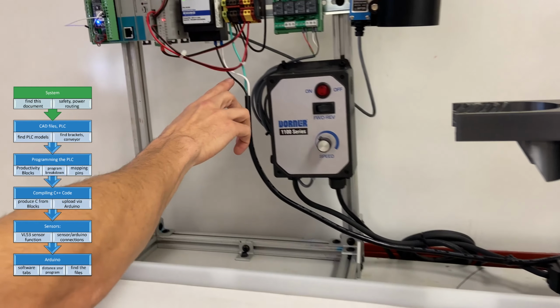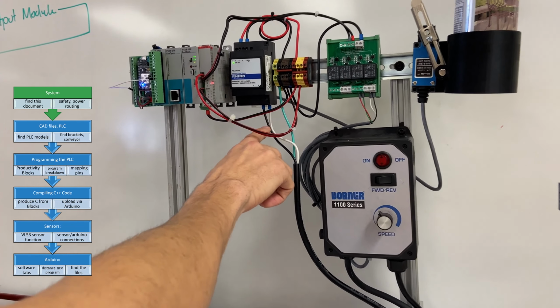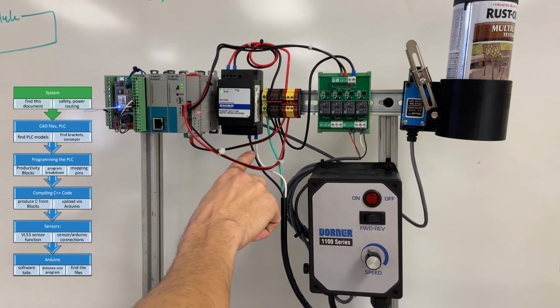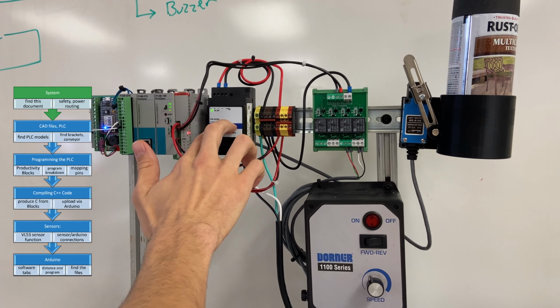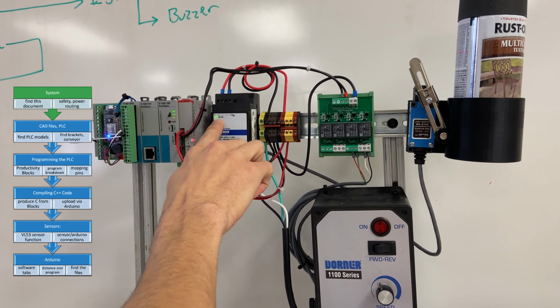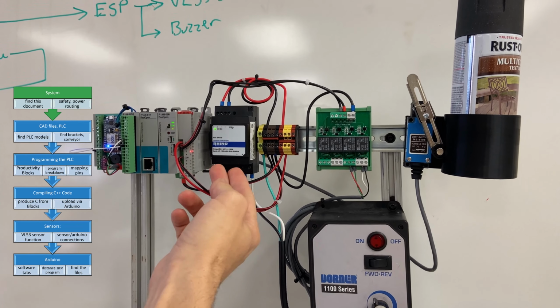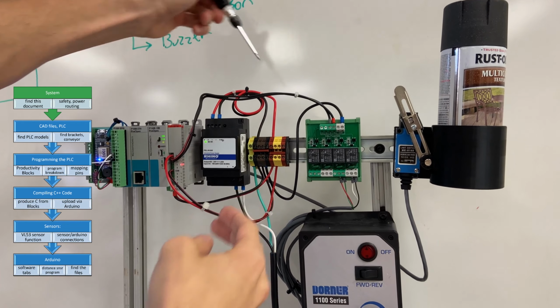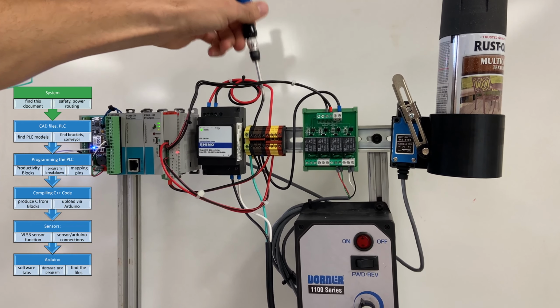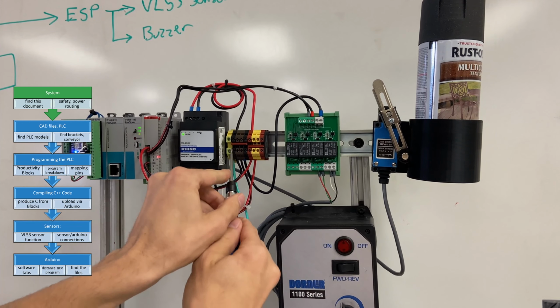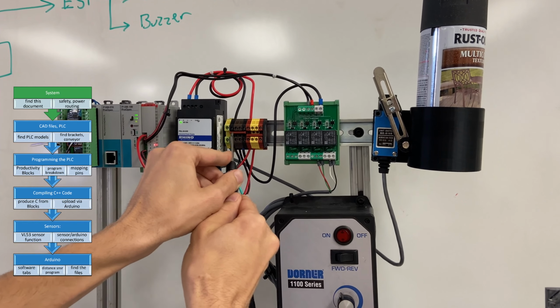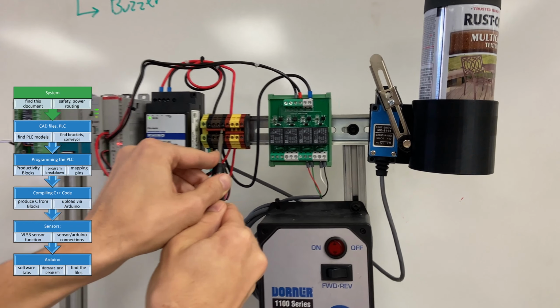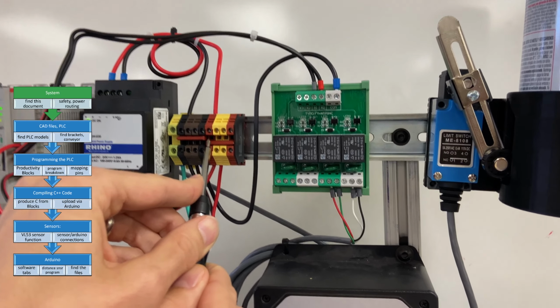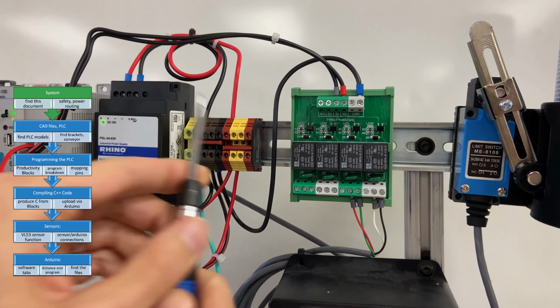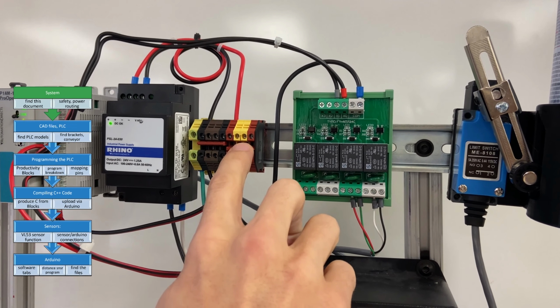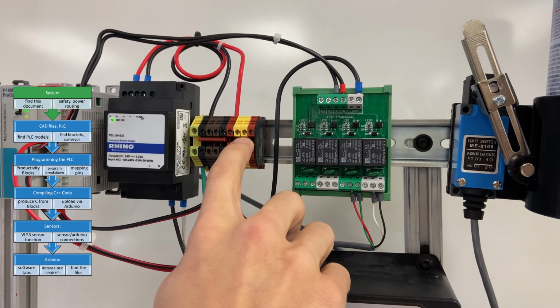Then secondly, we have 120 volts, neutral as white and hot on the black line, coming into this 24 volt power supply. And if this light comes on, that means the power is active coming in, and then you have 24 volts coming out of there and going into these junctions. The way this is laid out, you can notice this horizontal tab that's bridging all the connectors on this block, and this horizontal tab bridging all these connectors. So you have ground on the left and hot 24 volts on the right.